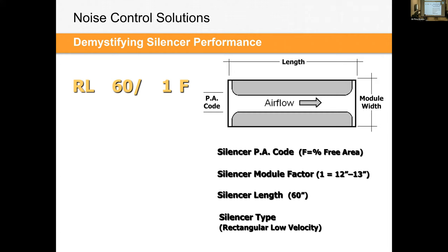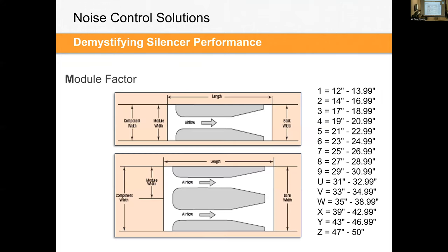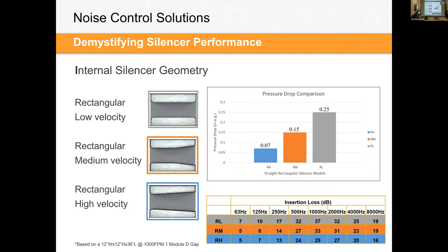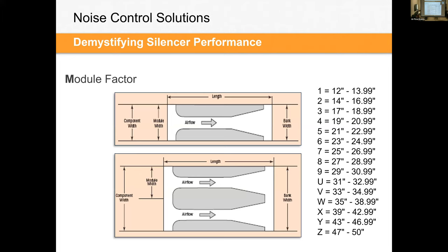So you don't have a test for every silencer? We don't. But what we've done is we've tested all these module factors. So if you can test the module and the geometry and the acoustic media and the length, you can build a database that gives you confidence in what the performance will be. Silencers are available in really infinite dimensions, from 6 inches to 50 inches in any 0.1 inch increment. What we've done is we've tested all these different module factors to give you that range of performance within those widths. And it works well.